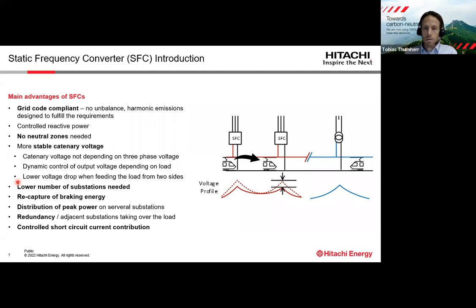And also because the SFC substations can feed in parallel, if there is a train in between two substations, this train is fed from both sides, and this means that the current from one side is only half of the current that we would have if it were fed by only one side. And this means that also the voltage drop along the catenary is reduced. So we get a more stable voltage because of that. And this can result in a lower number of substations needed, because a longer distance can be electrified per substation, because the voltage drop is lower.